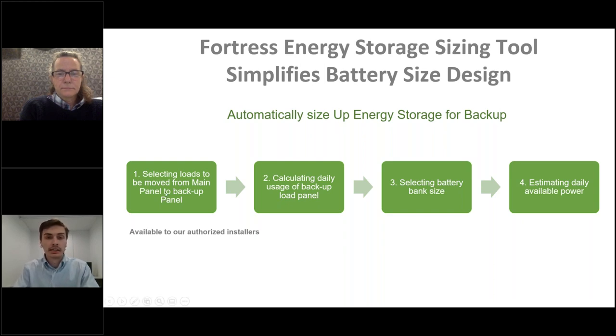General sizing guidance, let's assume this is for an emergency power application. You select the loads to be moved from the main panel to the backup panel, calculate the daily usage of that backup load panel, select the appropriate battery bank size for that usage, and then estimate the daily available power after your battery is sized.